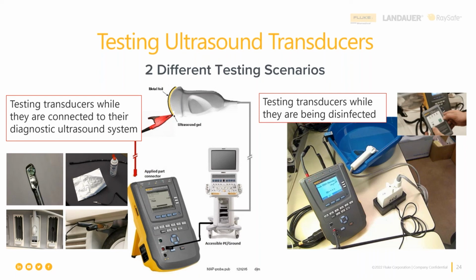One is when the TEE, or transesophageal echocardiograph transducer, is connected to the diagnostic ultrasound system, and we're going to do electrical safety measurements on the entire system, including this very special patient connection. So let's talk about the risk of injury to the patient from a TEE probe. The TEE probe, or transducer, is inserted down the esophagus of the patient so that it sits behind the heart and images out from behind the heart to look at the heart valves and their function, among other things.